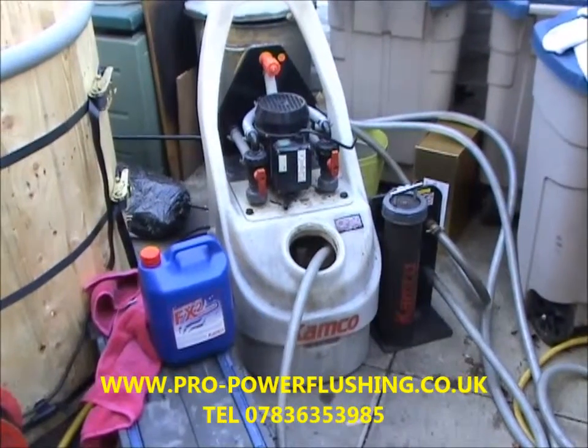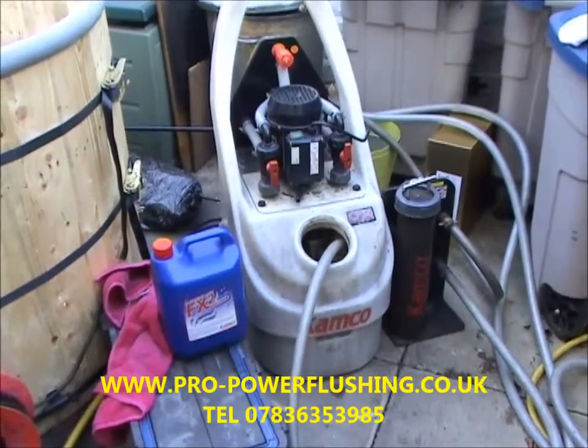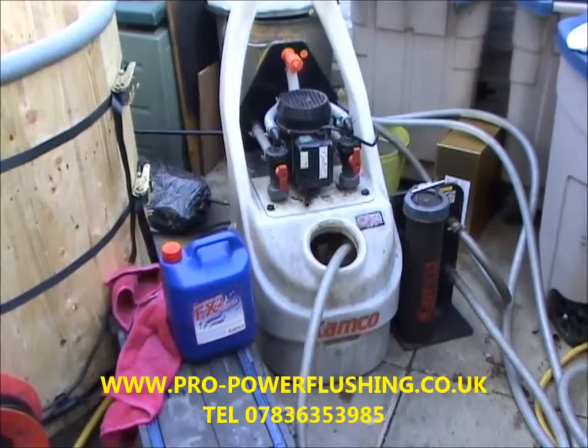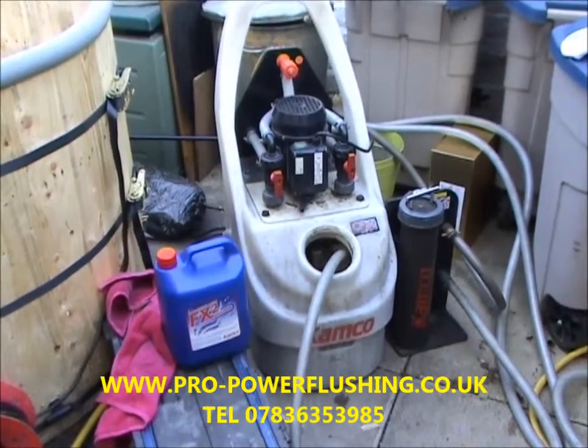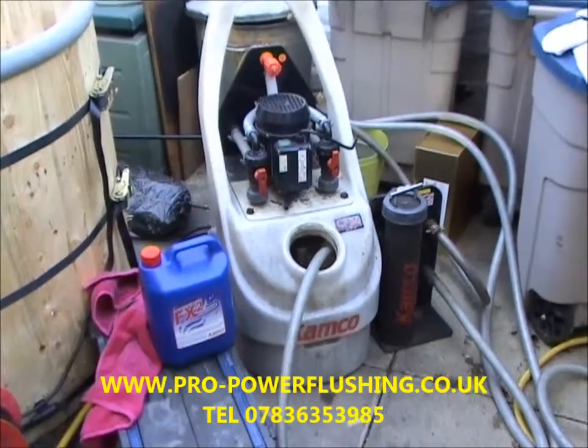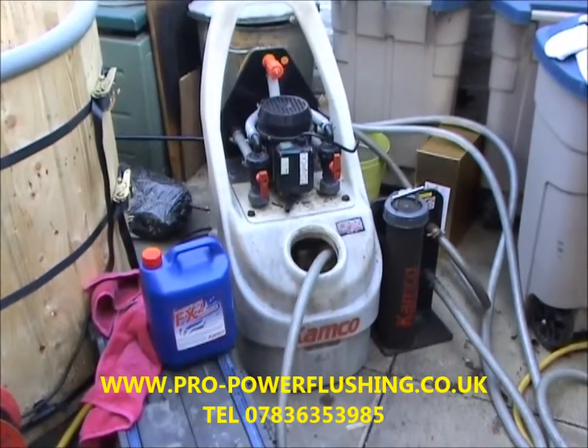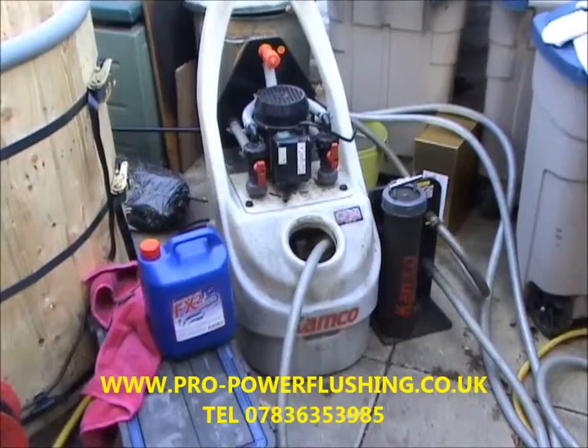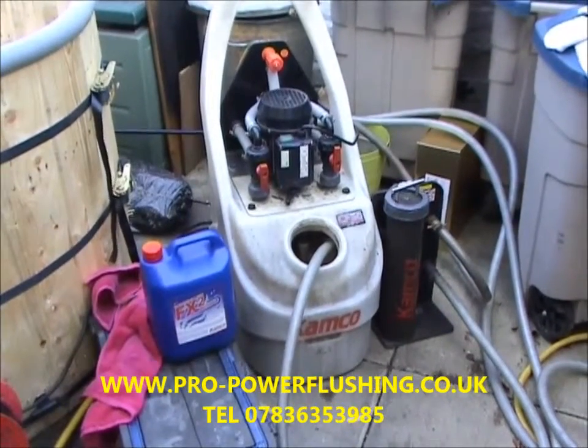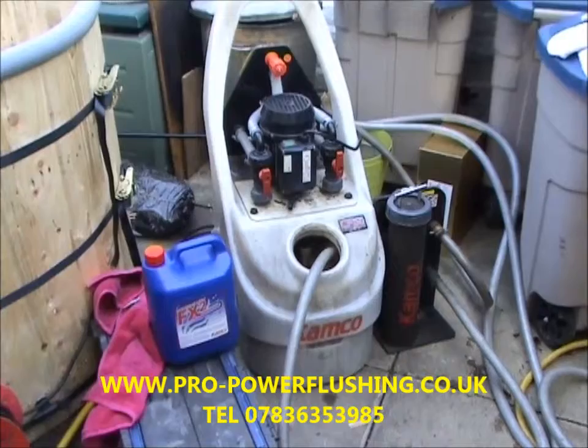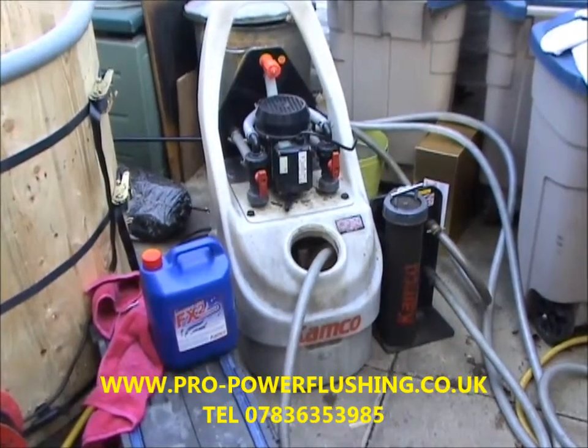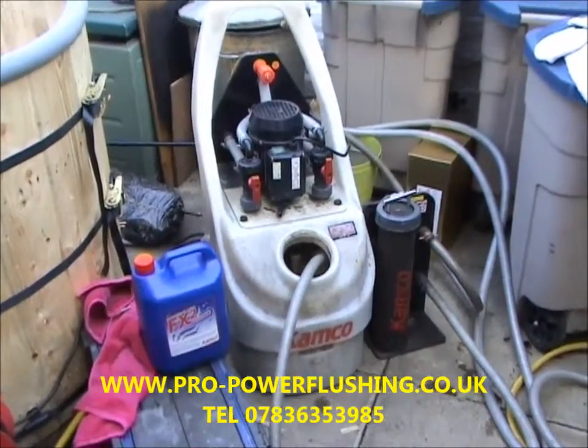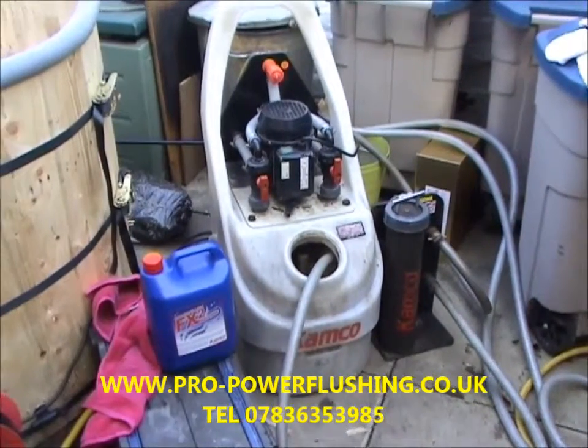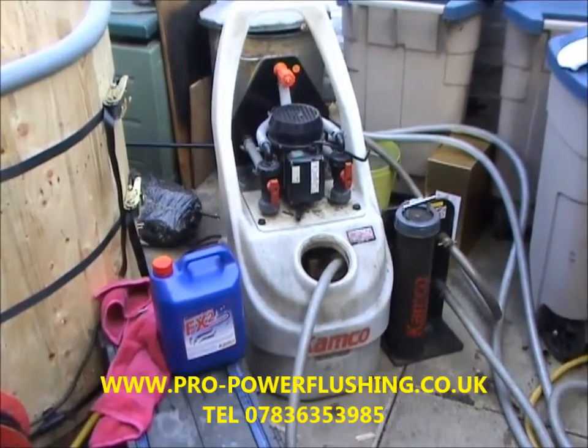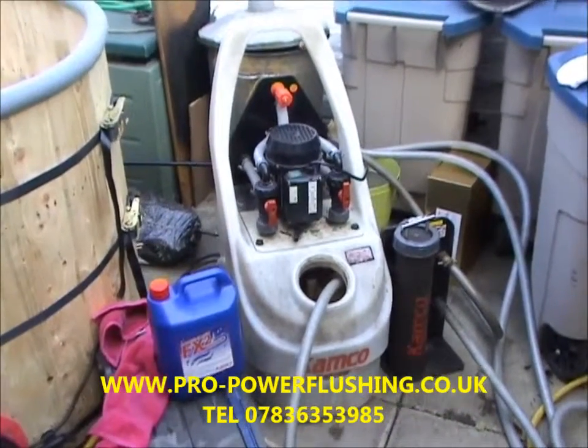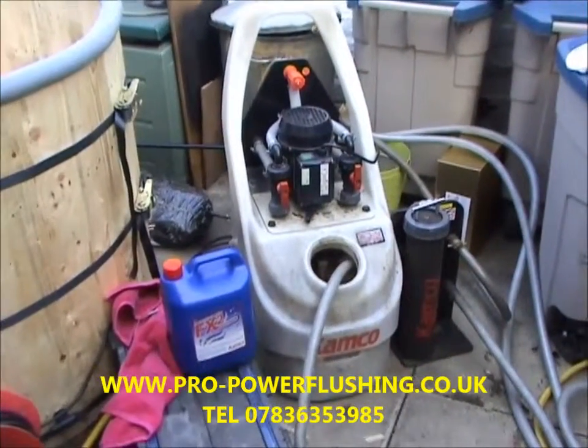Basically, power flushing, if it's done professionally, is the best thing you can do to your central heating system, getting all that rust and corrosion out. The benefits of power flushing are increased system reliability, quicker heat up times, a quieter running boiler, better circulation around your central heating system, and lower gas and energy consumption, so lower bills for you, the customer. Also, you need your system power flushed if you're having a new boiler fitted.